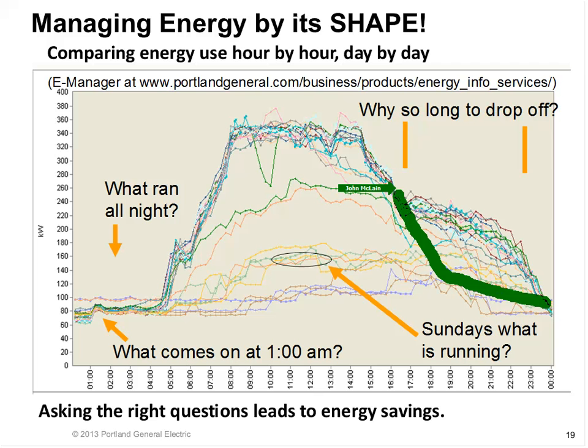And you're going to save all this energy in here. You can cut that off. So you can use the graph to ask a good question, make a change, and then measure, did I see a change in that shape or not? Very powerful stuff. The other thing they could ask from this is what ran all night long. Every night, every day, at about between 1 and 2 o'clock, something would come on and stay on. And they asked these questions, and no one had an answer.